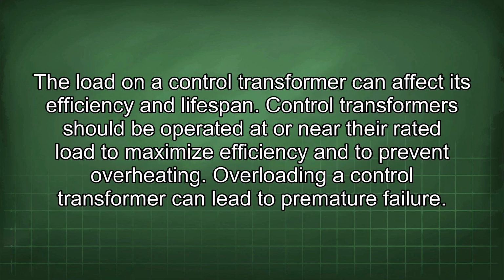The load on a control transformer can affect its efficiency and lifespan. Control transformers should be operated at or near their rated load to maximize efficiency and to prevent overheating. Overloading a control transformer can lead to premature failure.